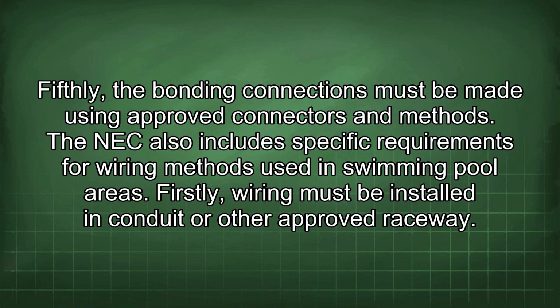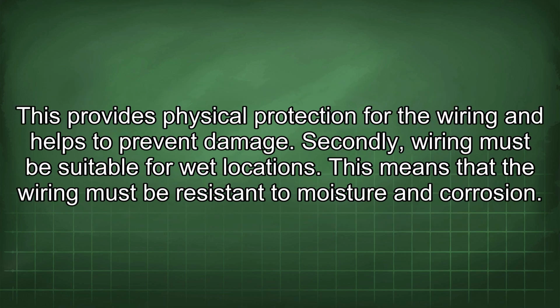The NEC also includes specific requirements for wiring methods used in swimming pool areas. Firstly, wiring must be installed in conduit or other approved raceway. This provides physical protection for the wiring and helps to prevent damage. Secondly, wiring must be suitable for wet locations. This means that the wiring must be resistant to moisture and corrosion.